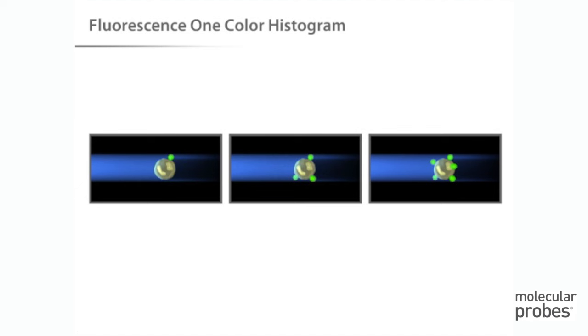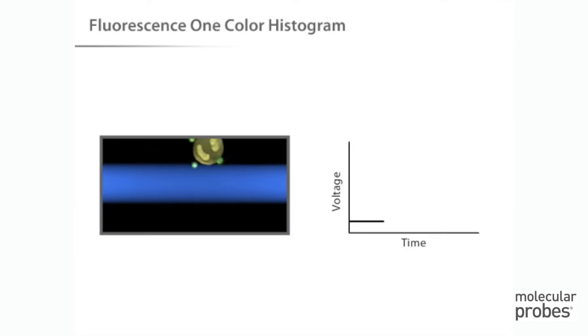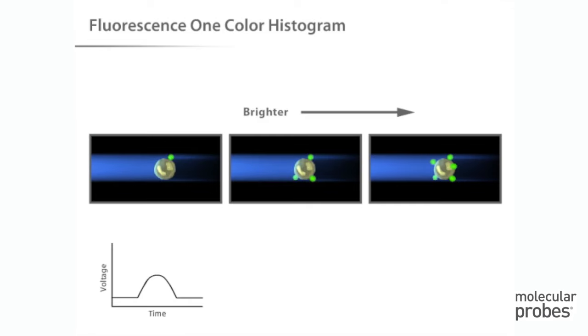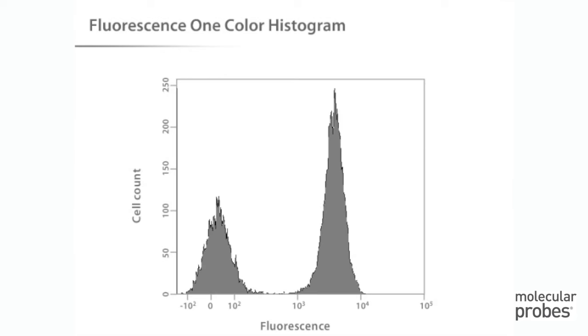Fluorescence data is collected in generally the same way as forward and side-scatter data. In a population of labeled cells, some will be brighter than others. As each cell crosses the path of the laser, a fluorescent signal is generated. The fluorescent light is then directed to the appropriate detector, where it is translated into a voltage pulse proportional to the amount of fluorescence emitted. All of the voltage pulses are recorded and can be presented graphically.